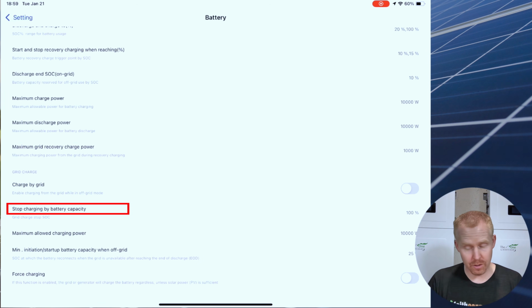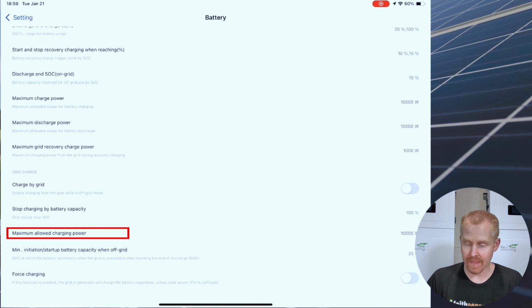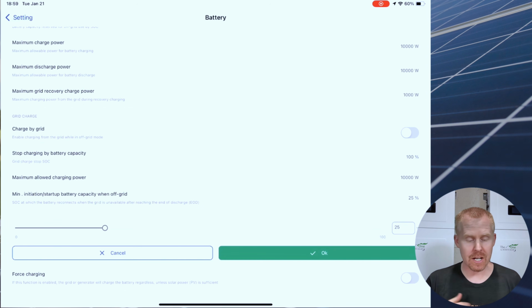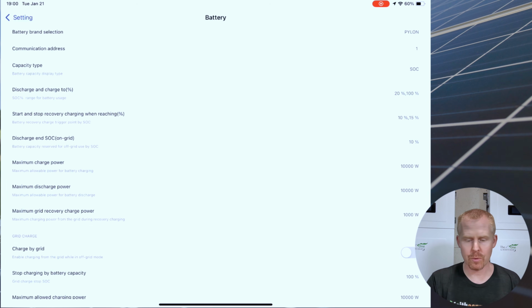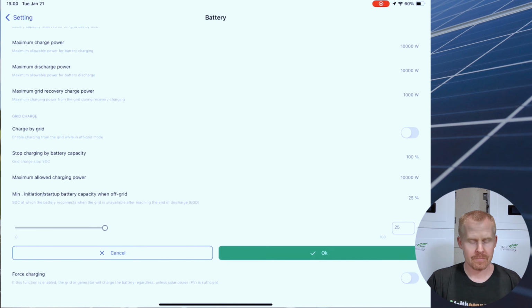Stop charging value, again, same thing. Maximum power, 10,000 watts to charge from the grid. Minimum initiation startup battery when off grid. So this field is designed to require your battery to be at a certain percentage if you hit that end of discharge shutdown value. That discharge down to right now is set to 20%. And if you have no grid connection, it wants your battery to get up to 25% before it allows your inverter to turn on and start inverting power.